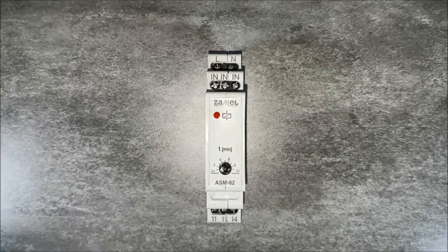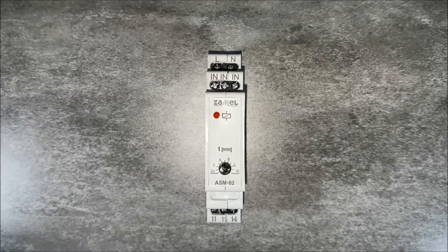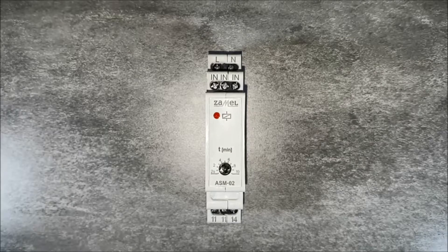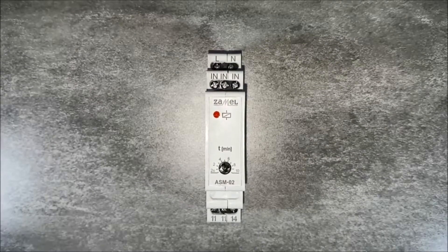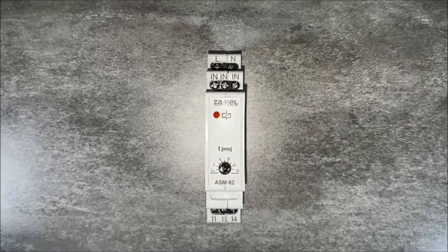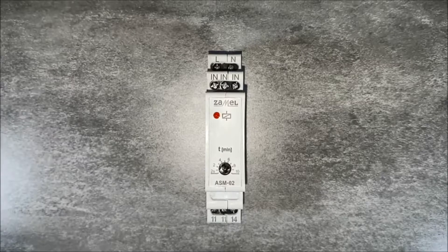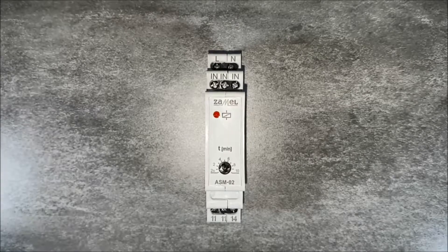The triggering signal is the phase signal applied to the IN terminals. The ASM02 Staircase Relay has a built-in 16-amp normally open type relay. The device works with illuminated buttons with a total current not exceeding 200 milliamps.